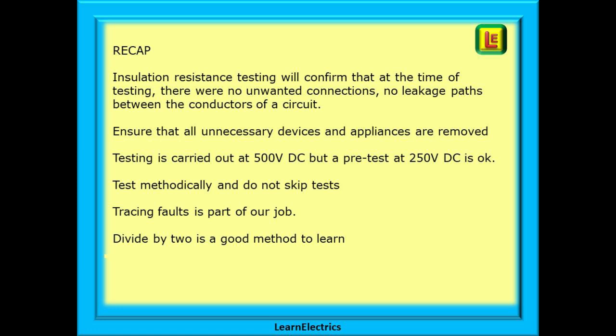And there we are — a simple introduction to insulation resistance testing. Insulation resistance testing will confirm that at the time of testing there were no unwanted connections and no leakage paths between the conductors of a circuit. You must ensure that all unnecessary devices and appliances are removed, and the testing should be carried out at 500 volts DC, though a pre-test at 250 volts DC is okay. Test methodically — do not skip the tests. The tracing of faults is a necessary part of the job; the more you do it, the better you become.